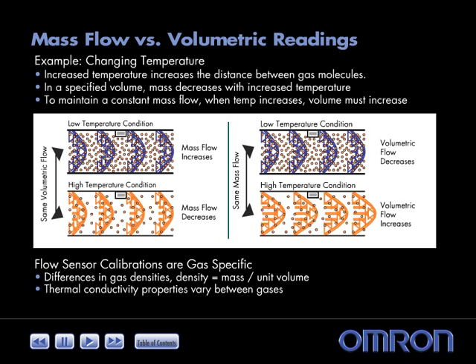Density is defined as mass per unit volume. Because different gases have different densities and thermal conductivity properties, it is important to pay attention to the calibration gas specified on the datasheet when sizing OMRON flow sensors. Contact OMRON for assistance in choosing an appropriate flow sensor for a gas other than that specified.